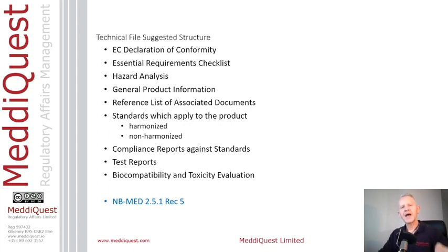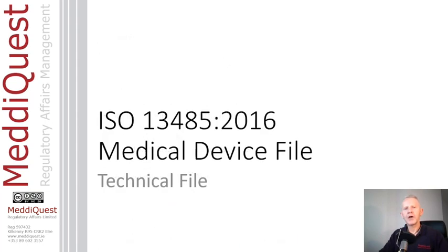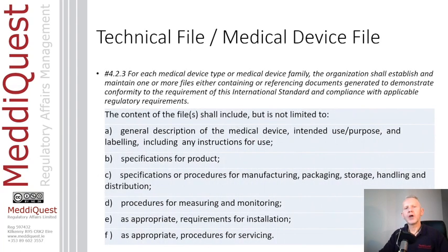Very clearly, keep this in mind. This was a suggested structure for the technical file, but it's not mandated. You need to structure it to suit your products.